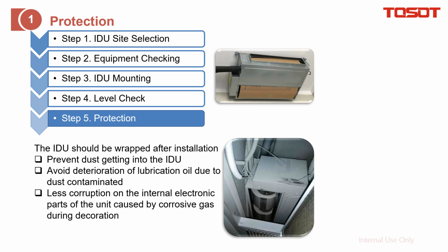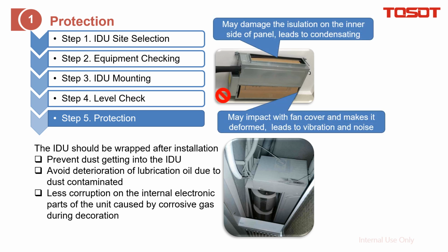Actually it is no good because the cardboard may damage the inside insulation. If the inside insulation is damaged, it will later lead to condensing water generating on the surface of the panel. And it especially happens inside the ceiling. We're just afraid that the condensing water may damage the ceiling.